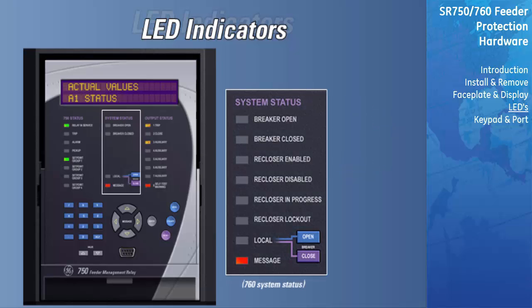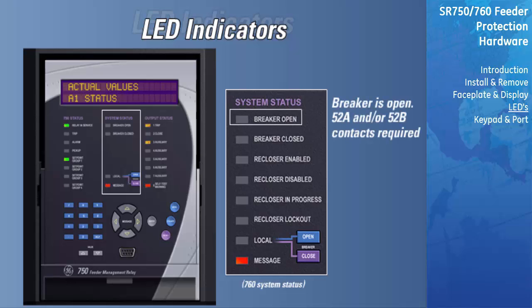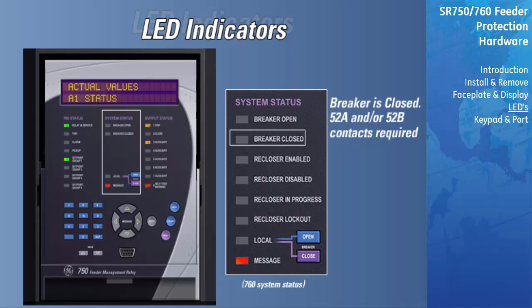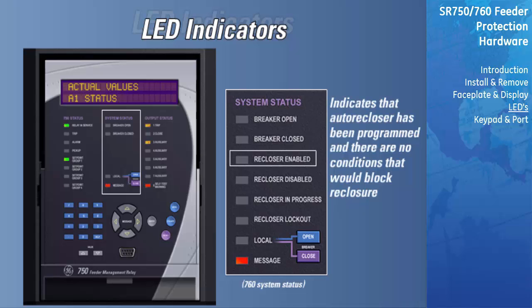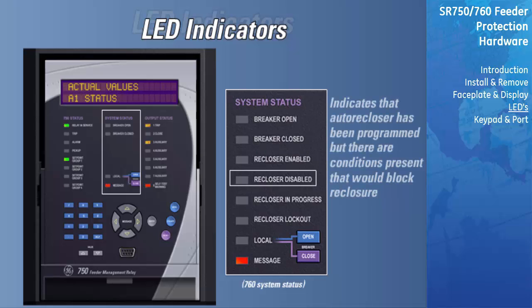System Status LED Indicators. The Breaker Open LED indicates that the breaker is in the open position based on auxiliary contact feedback. The Breaker Closed LED indicates that the breaker is in the closed position based on auxiliary contact feedback. The Recloser Enabled LED indicates that auto reclosure has been programmed and there are no conditions that would block reclosure. The Recloser Disabled LED indicates that auto reclosure has been programmed, but there are conditions present that would block reclosure.